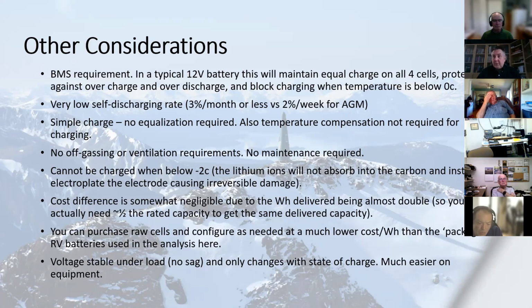Another real benefit to the equipment connected to it is that the voltage is very stable under load. Just anecdotally, with my AGMs in my camper, if the furnace was running (about a 6 amp load) and the lights were on (maybe a couple amp load), and you turned on the water tap slowly so the water pump was surging and drawing about 10 amps, you could see the lights dimming as the pump surged. With the lithium iron phosphate, the voltage is absolutely rock solid regardless of load - it doesn't sag at all. That makes it a lot easier on electrical systems, which certainly prefer that stable voltage supply. So load sag just isn't a factor with lithium iron phosphate.